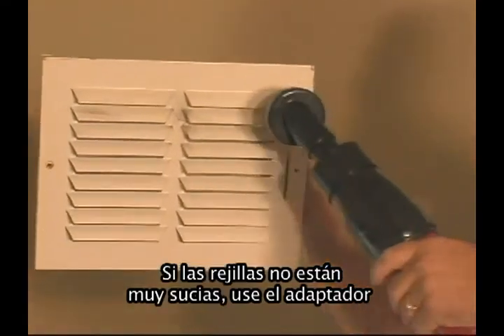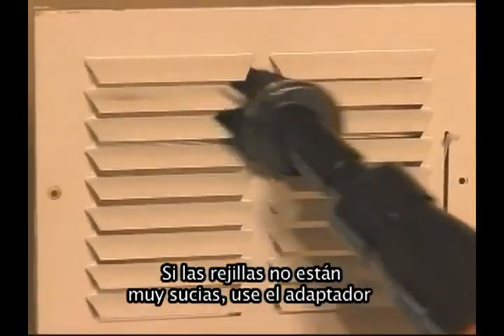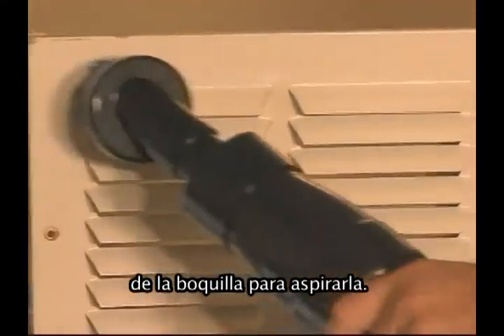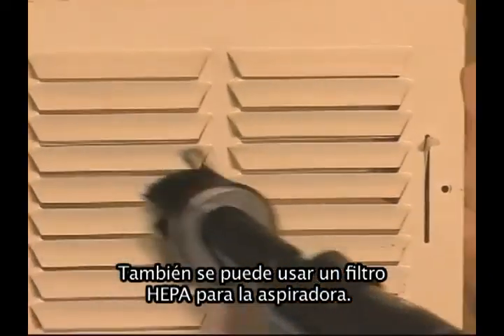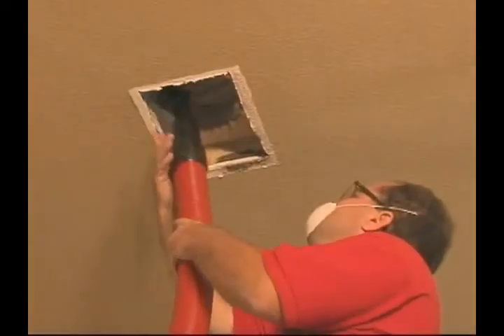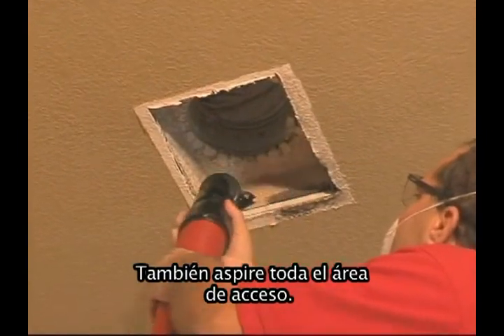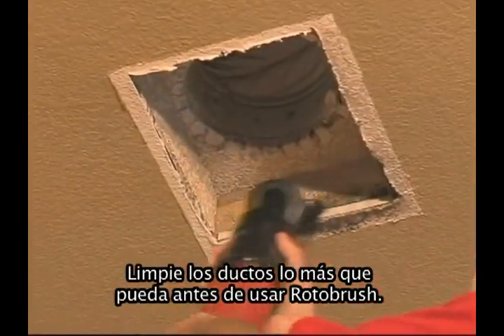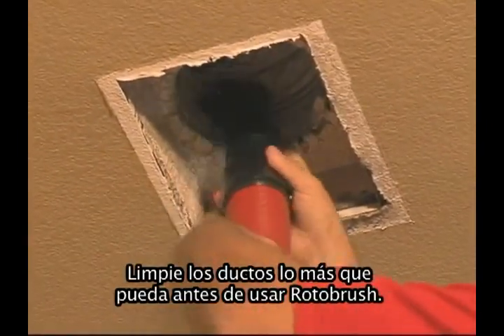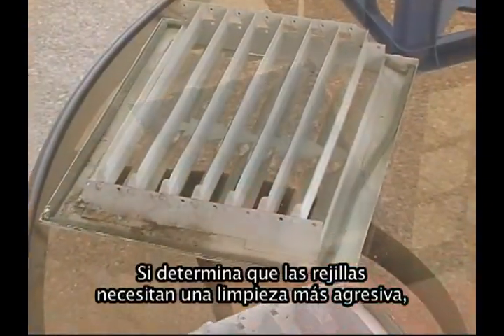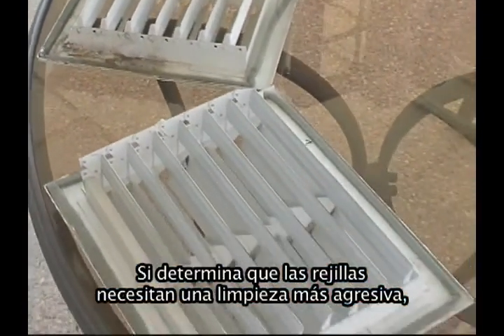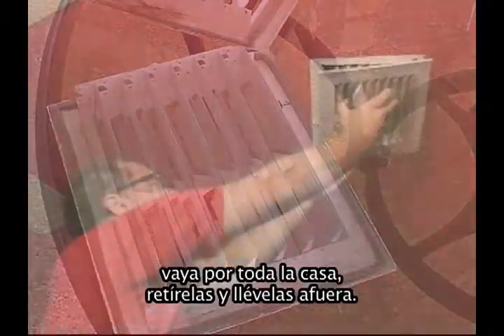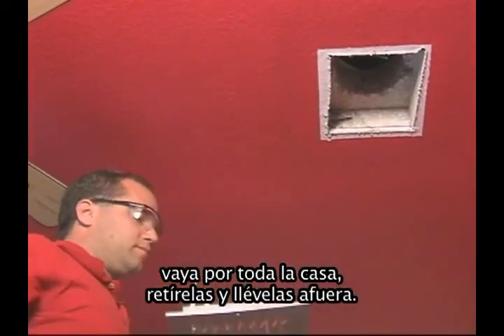If the registers are not heavily soiled, use the Rotobrush nozzle adapter and dust brush to vacuum. You may also use a HEPA filtered shop vac. Also, vacuum out the boot area. Clean in the air duct as far as you can prior to cleaning with the Rotobrush. If you determine the register covers are going to need more aggressive cleaning, go through the house, remove those, and take them outside.